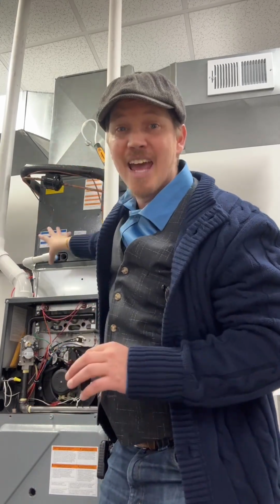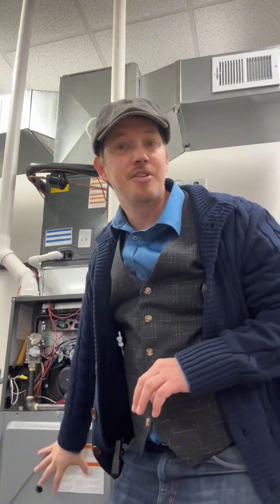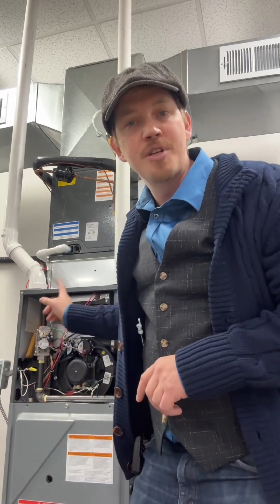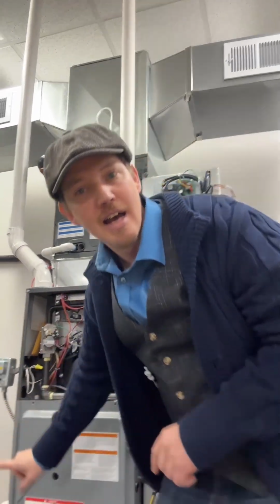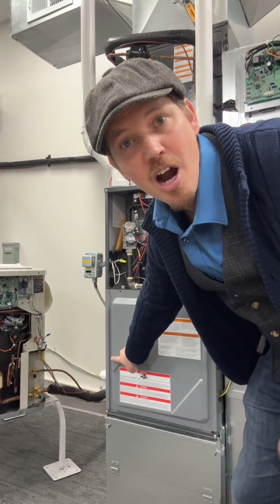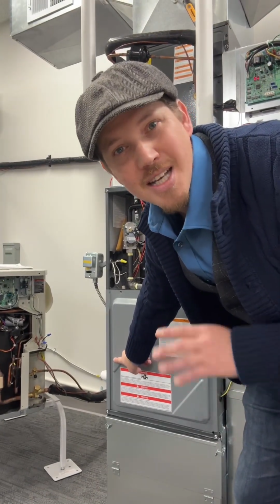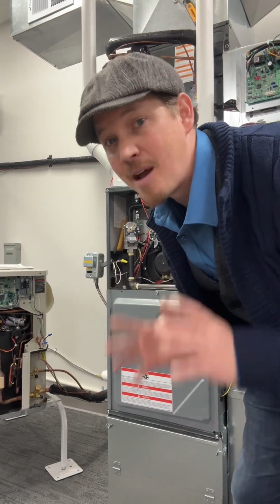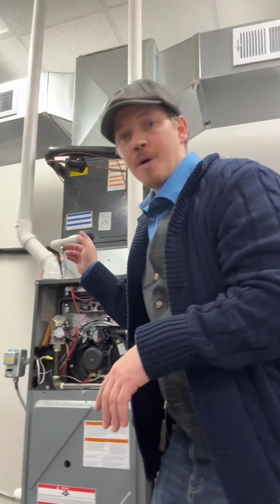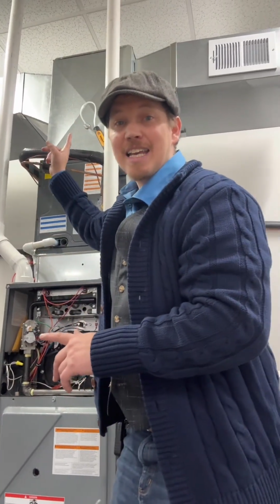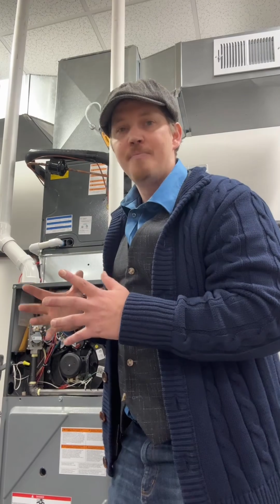The ductwork and this coil are both external to this. So my numbers between here and here are my total external static pressure, because it's reading everything that's not my furnace. My pressures between here and here, that's just my coil drop. How much is the coil itself stressing out the system? That can tell me things like, is my coil dirty? It can also tell me things like, is it the right coil?